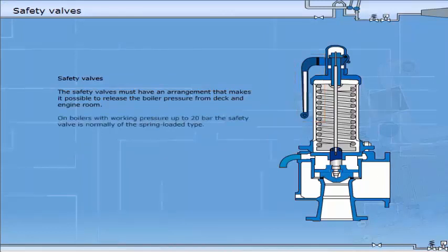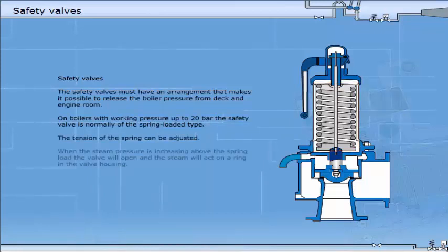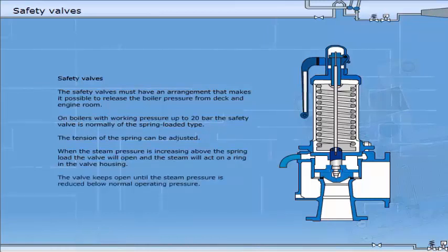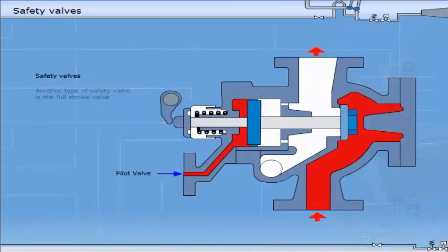On boilers with working pressure up to 20 bar, the safety valve is normally of the spring loaded type. The tension of the spring can be adjusted. When the steam pressure increases above the spring load, the valve will open and the steam will act on a ring in the valve housing. The valve keeps open until the steam pressure is reduced below normal operating pressure.